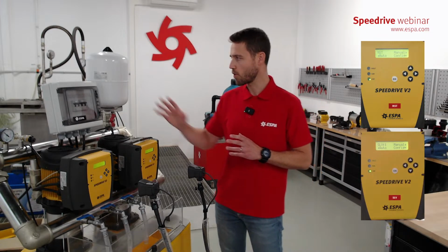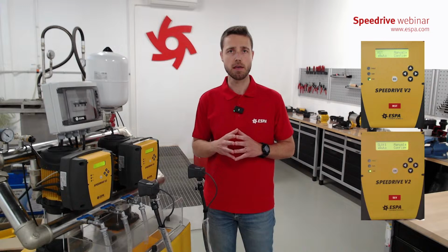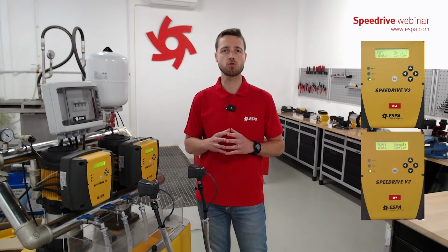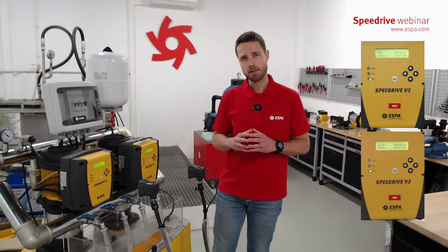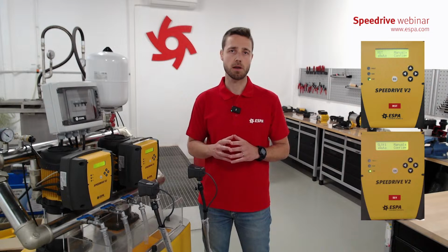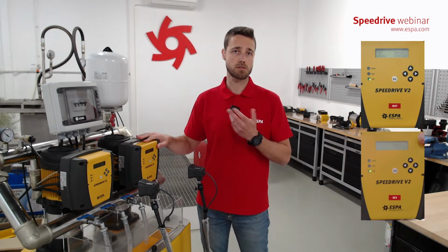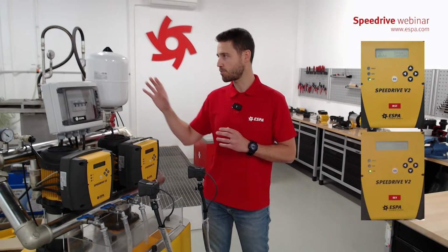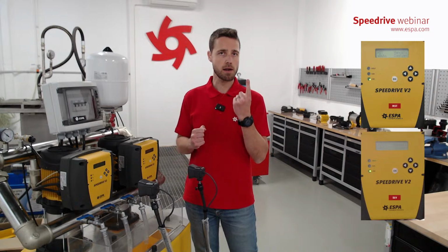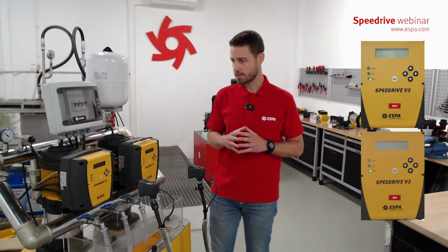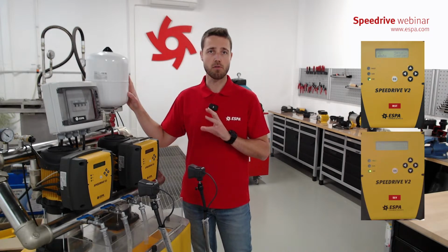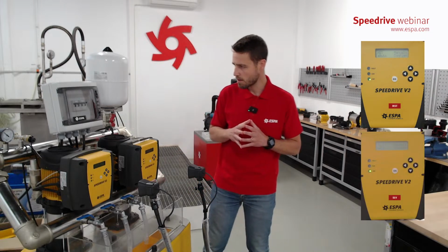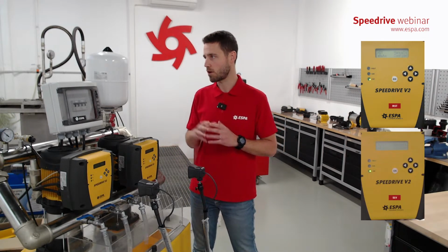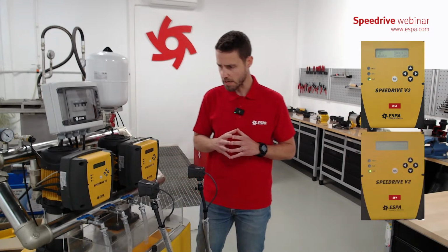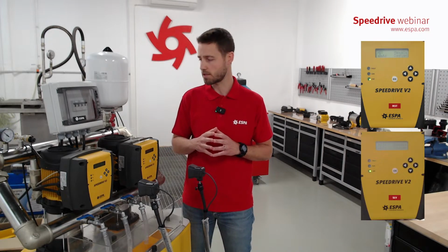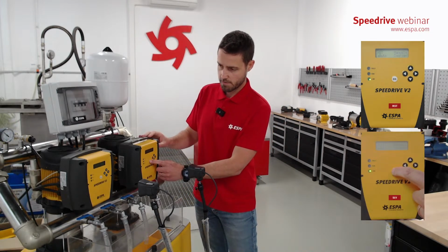And also, we have this tank, this vessel. It has to be inflated or deflated according to the duty point of the pump. Normally, it has to go below the duty point. For example, if you have 3 bars set up in the Speedrive, then the pressure in the tank has to be around 2 bars, 1 bar below. To check the pressure of the tank, the manifold has to be empty, because otherwise we will be reading the pressure in the system. So normally you can leave a valve open to empty the installation. Now, let's see both Speedrive.